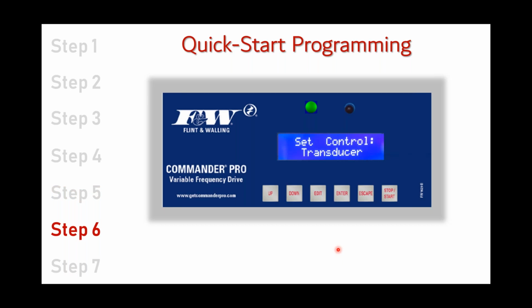And then the last of the menus, the very last one, it's going to ask you to set control. And again, you're going to use your up and down buttons, and you can scroll between transducer and switch. I mentioned early on that this drive can operate off of either one. And I also mentioned that the switch is, I think, probably, I don't know if we'll even be selling it 1.5 years from now. I think the popularity of it's going down. Everybody's liking the transducer. Had I selected switch here, if I'd have used my up and down buttons and selected switch, the next thing that's going to pop up on my screen is it's going to say press start to continue. And I'm done. I'm done with the programming.